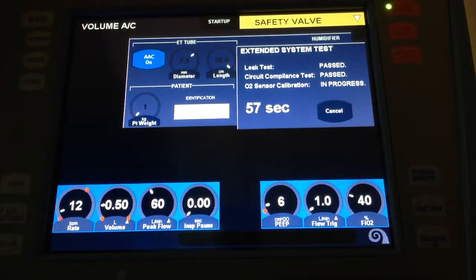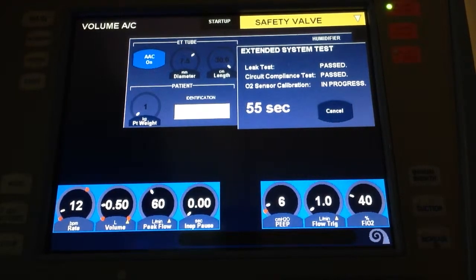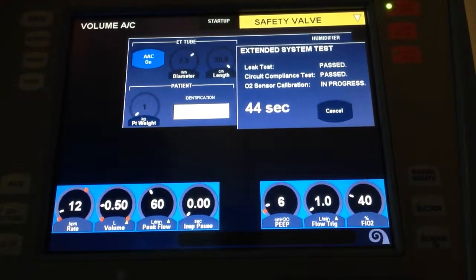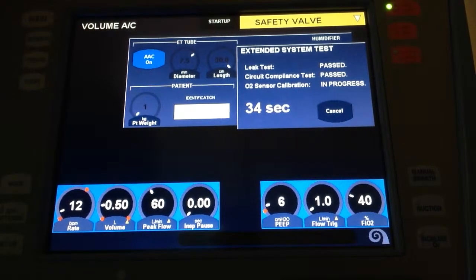Whenever you do any of these tests, you want this circuit as complete as possible. If you're going to use an HME, you want an HME in line. A lot of them are saying to hook up the active humidifier to do it, but I know that a lot of the humidification chambers will leak. If you have water in the system and have already spiked the bag, spiked the bottle, that's different. That will seal the system, and you go ahead and try it. But for the purposes of the test and for this lab, we're not going to hook up the active humidification.